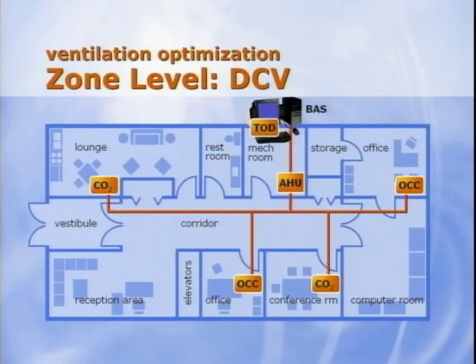Finally, zones that are sparsely populated or have predictable occupancy patterns may be best controlled using a time-of-day schedule in the building automation system. This schedule can either indicate when the zone would be normally occupied versus unoccupied, or may even be used to vary the zone's ventilation requirement based on anticipated population. These various zone-level DCV strategies are used to reset the ventilation requirement for their respective zones for any given hour. This zone-level control is then tied together using ventilation reset at the system level.